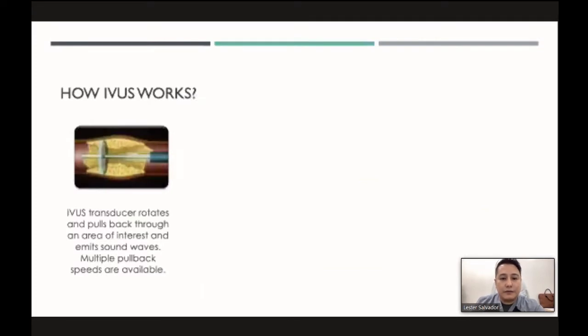So how does IVUS work? A catheter pulls back through a lesion or an area of interest and results in a series of tomographic cross-sectional images of the vessel. The catheter has a transducer that is mounted at the tip. A transducer converts one type of energy to another, in this case, electricity to sound. An ultrasound signal is produced in the transducer by passing an electrical current through piezoelectric crystals, a material that expands and contracts when electricity is given. The images are formed through interpolation.